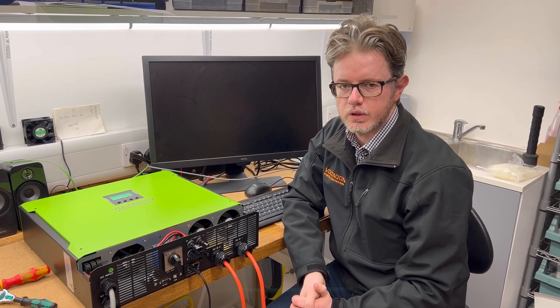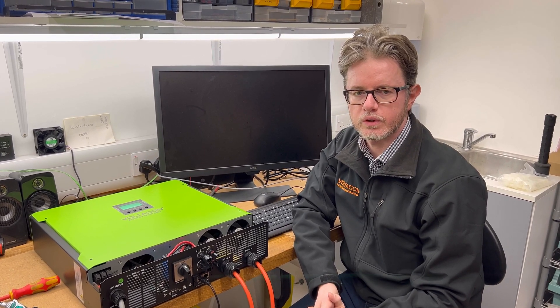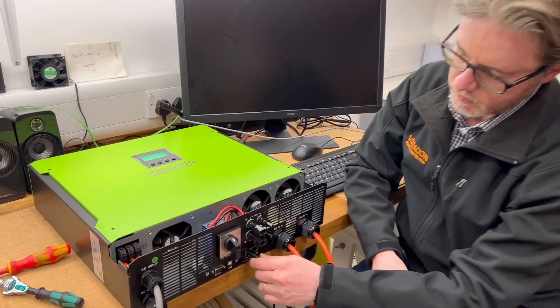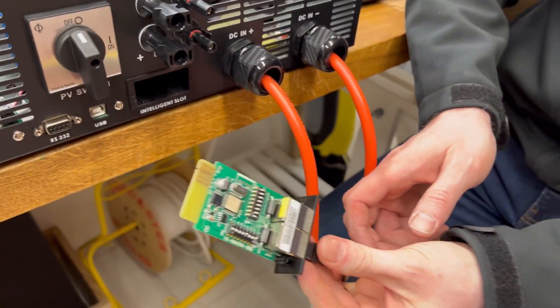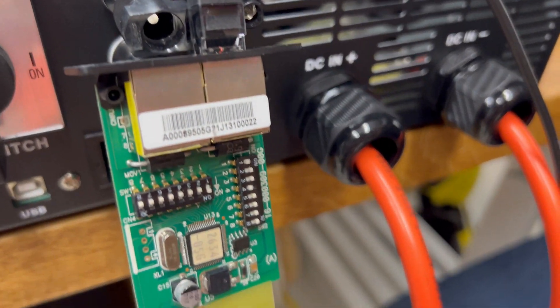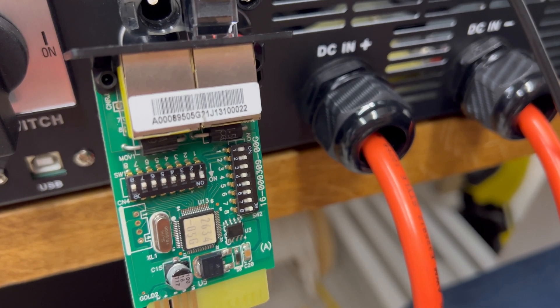Hello. In this video I'm going to show you how to pair PylonTech lithium-ion batteries with our hybrid 5.5 kilowatt solar inverter using the BMS communication card. We use the intelligent port of the inverter to install the Modbus card, and here you can see the pin configuration. It's very important to follow this sequence in order to match the BMS of the battery.